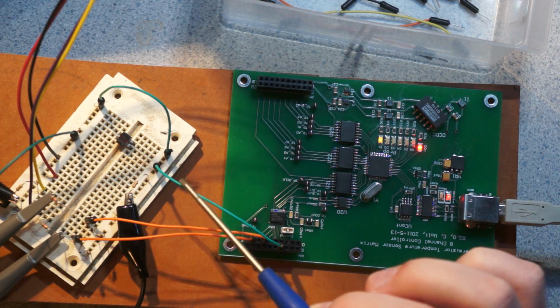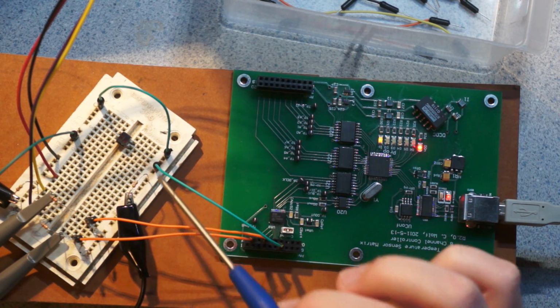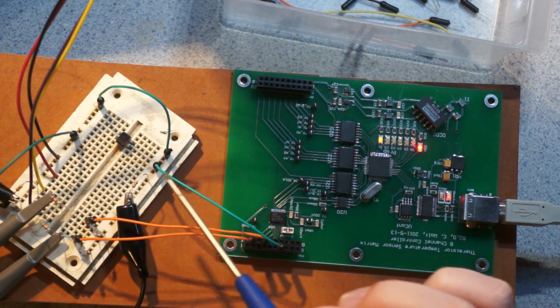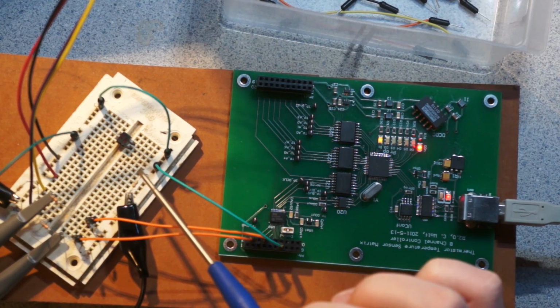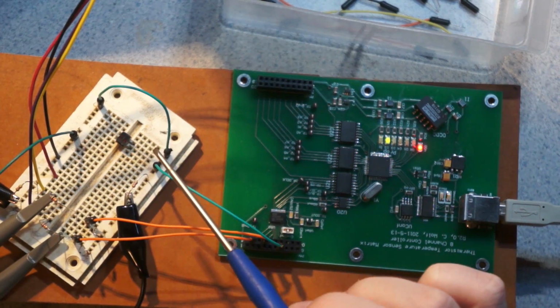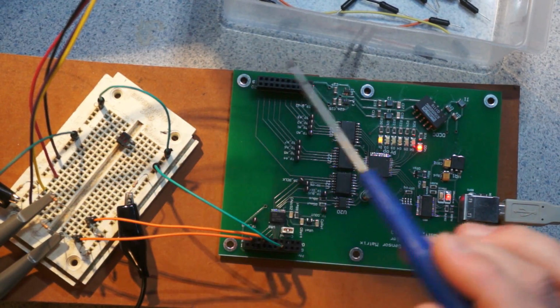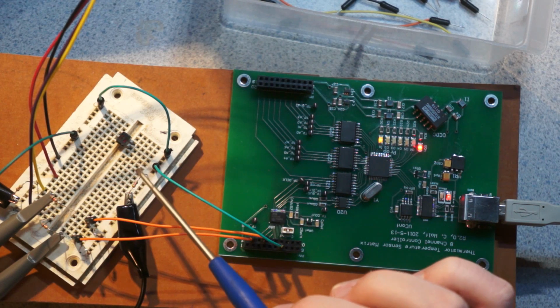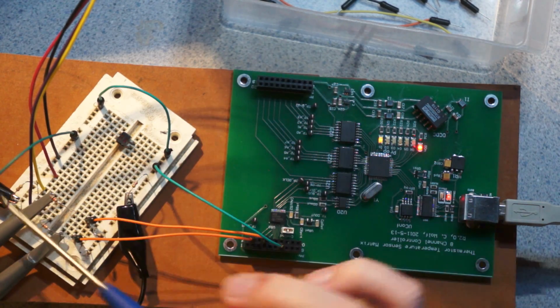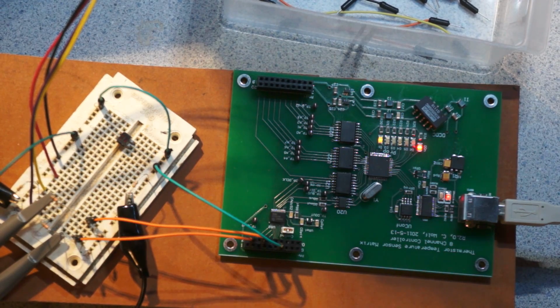So obviously this is kind of a rather dangerous way of doing this. I was very careful to check that the voltage on the ground, quote unquote, coming out of the Kill A Watt is indeed neutral rather than hot. Because if the wiring in the house is backwards, you could very easily have 120 volts - I'm in America, so it's 120 volts - on the neutral lead, which would make the whole thing hot and shock the shit out of you if you touch anything. So before I did anything, I was very careful to double check and reference against ground and so forth.